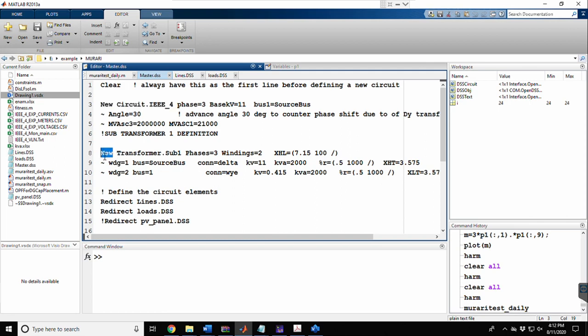I have connected a delta-star transformer. The 'new' command is used to create any element, so 'new transformer' is used here. The transformer name is 'sub1', it has three phases and two windings. Winding one is connected to the source bus with a delta connection at 11 kV and 2000 kVA capacity. Winding two is connected to bus number one with a star connection at 0.415 kV and the same kVA rating.